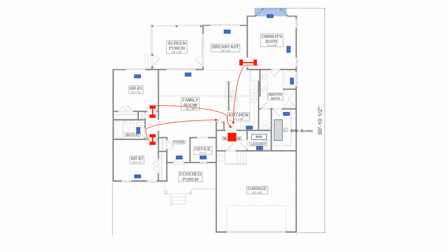It accomplishes the same thing as individual returns, but with less ductwork in the house, resulting in lower static pressure, better performance, and lower material and labor costs. If your project allows you to use 1 or 2 central returns and jumper ducts for the rest of the rooms, I strongly advise that you use that strategy.